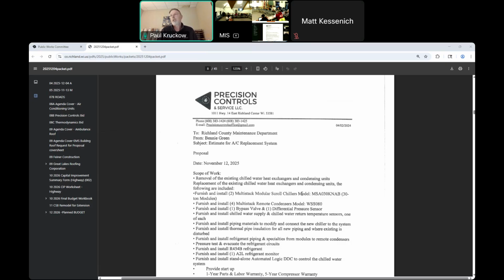A modular chiller gives you the flexibility to have the indoor compressor portion of a chiller inside the building, getting it through doorways where you have tight quarters or limited space to work with. You currently have 50 tons of cooling. We're proposing two 30-ton Multi-Stack modules that will give you a total of 60 tons of cooling, a little more capacity than you currently have.